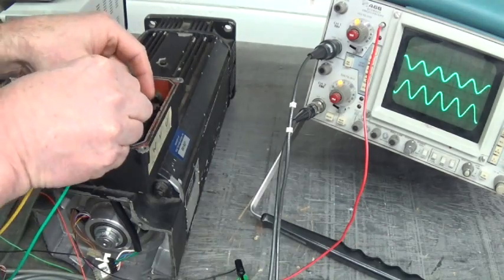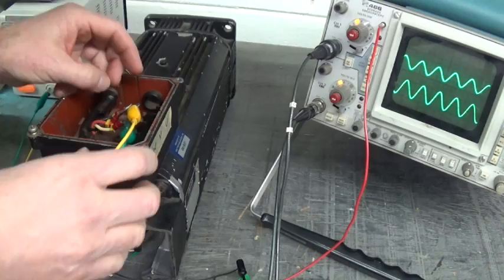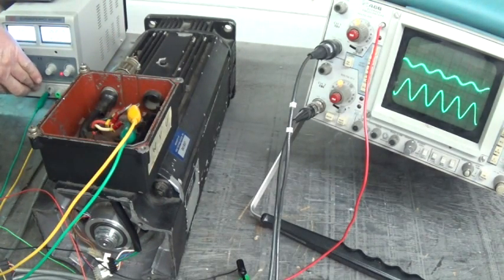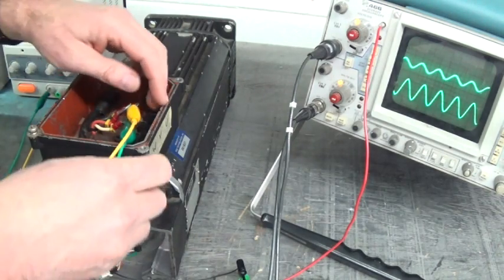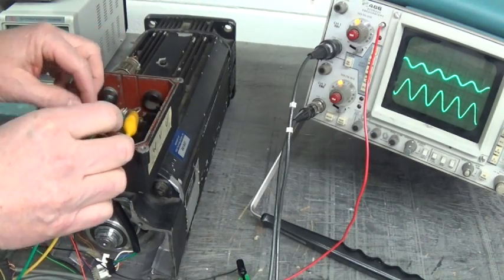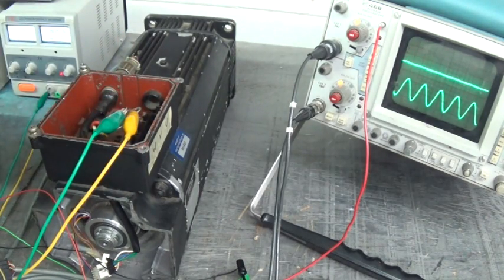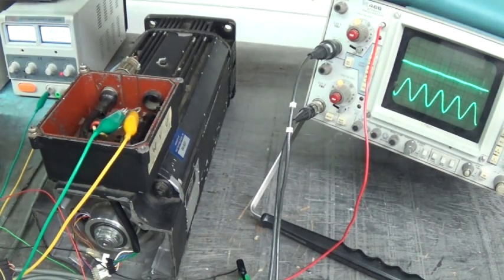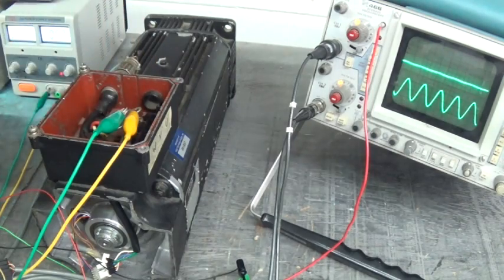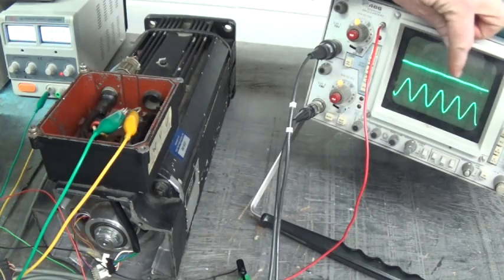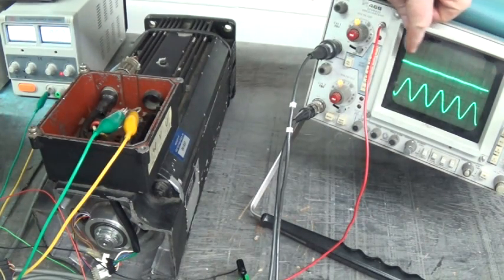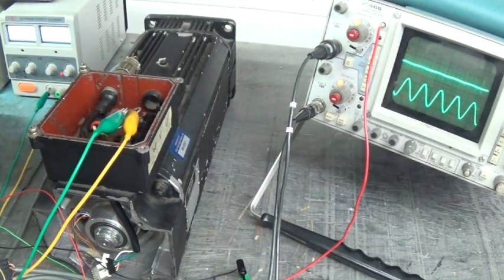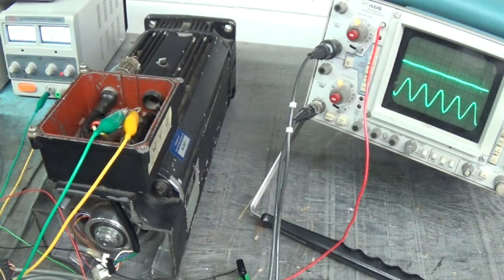Let me take the positive over to U. Nope, not yet. Let's take ground over to V. There we go, we found it. Okay, so positive on U, ground on V gives us a flat line condition. The sine is flat lined and the cosine is at max.